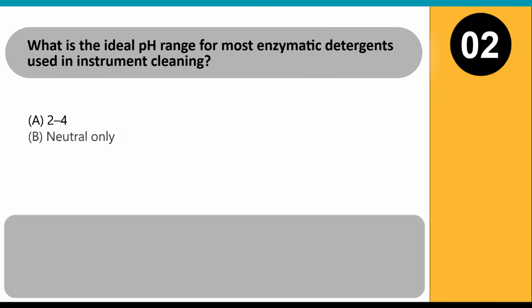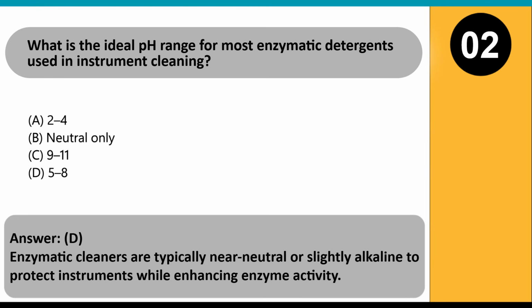What is the ideal pH range for most enzymatic detergents used in instrument cleaning? A. 2 to 4. B. Neutral only. C. 9 to 11. D. 5 to 8. Answer D. Enzymatic cleaners are typically near neutral or slightly alkaline to protect instruments while enhancing enzyme activity.